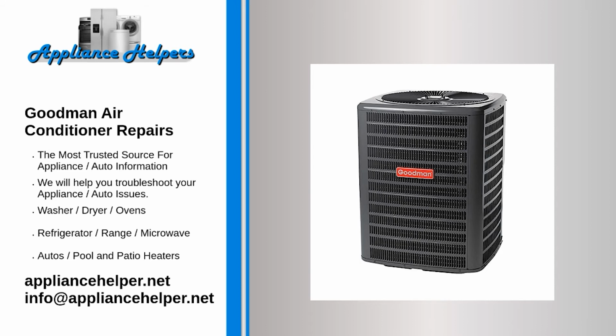Goodman condenser fan motor does not run. If the capacitor is defective, the fan motor might be noisy, overheat, or not run at all. To determine if the capacitor has failed, inspect the capacitor. If the capacitor is bulging or leaking, replace it. Goodman condensing unit does not run. The wall thermostat has contacts in it that control the furnace. If the contact fails, it can result in the furnace and condenser unit not running at all.